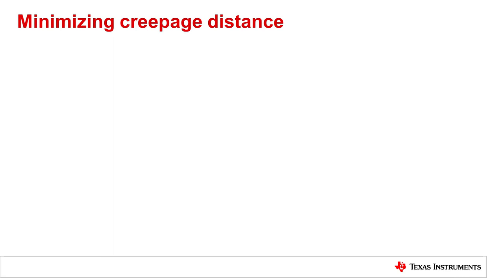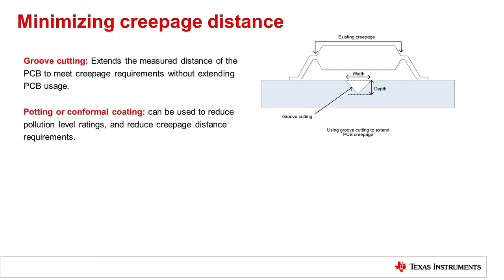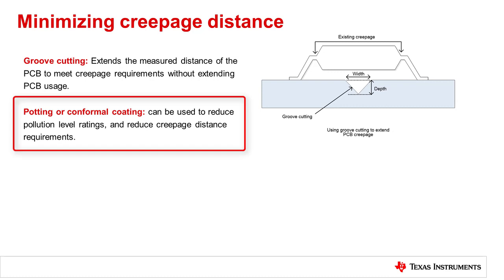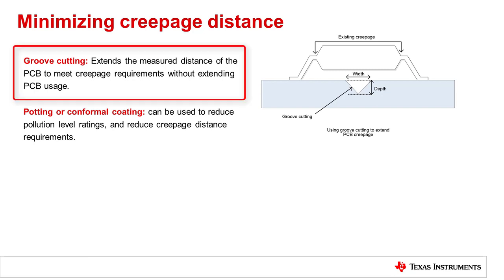It is worth noting that there are some techniques that have been used to reduce creepage and clearance requirements. For example, conformal coating or potting techniques involve the deposition of insulating polymer or other material over the printed circuit board and have historically been used to reduce pollution degree around the isolator. This reduces the requirement on creepage and clearance by eliminating the influence of pollutants. Other techniques, such as groove cutting, can be used to attain a lower PCB creepage distance. Groove cutting effectively extends the creepage distance.